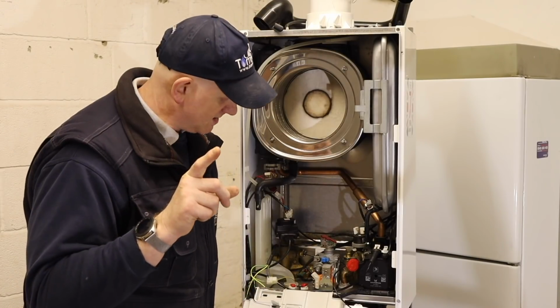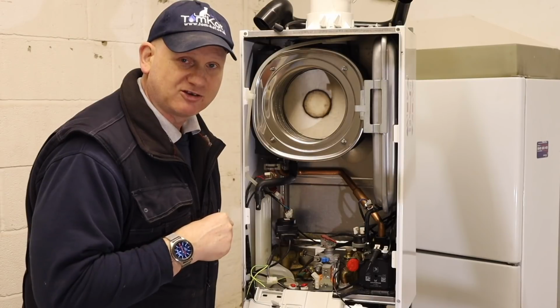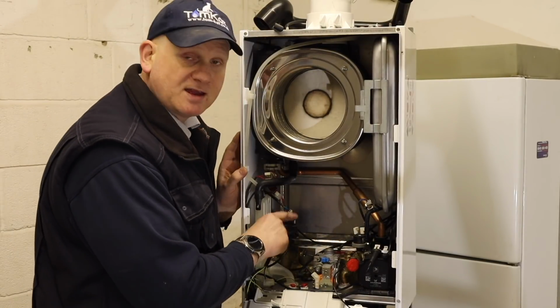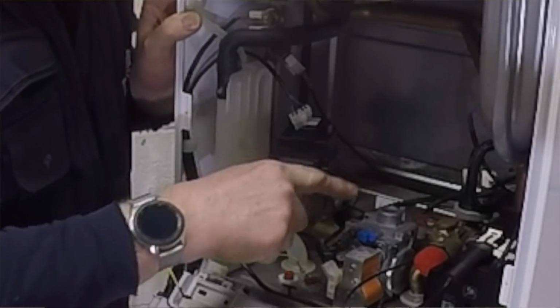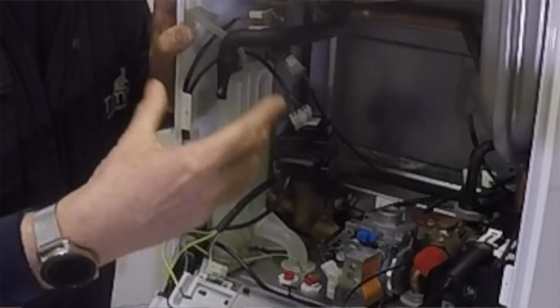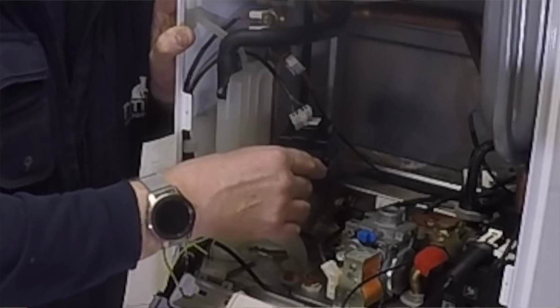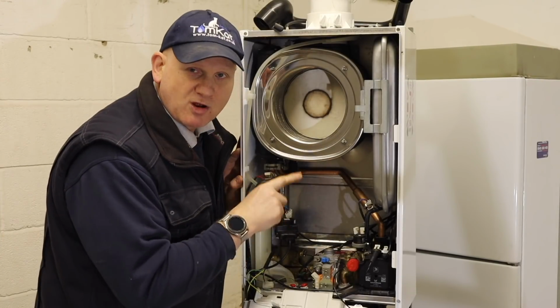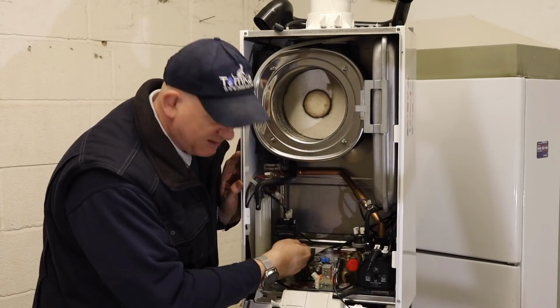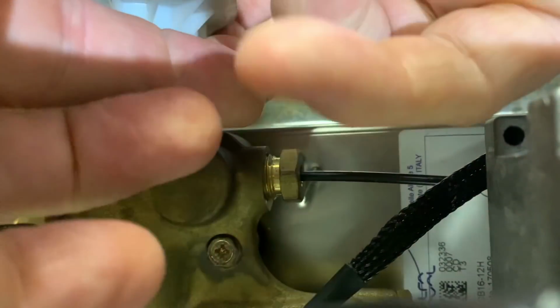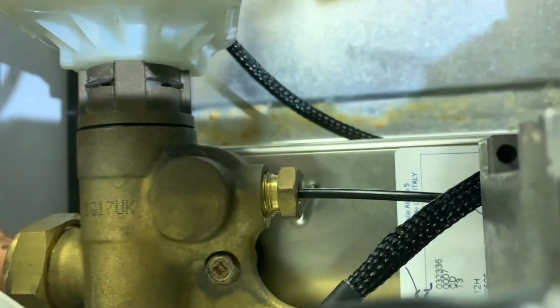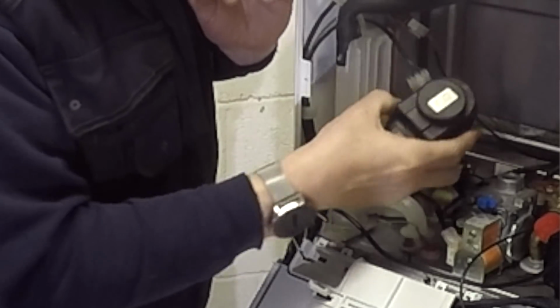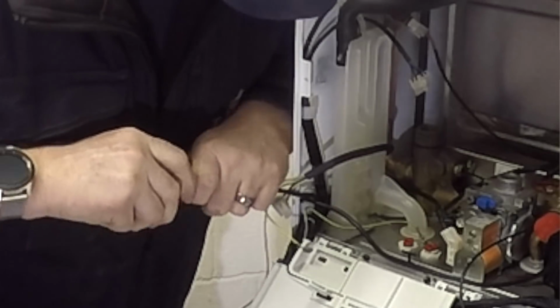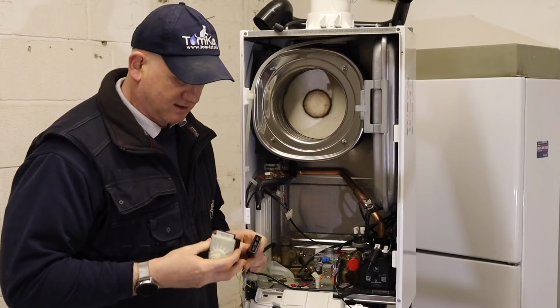So that's the flow turbine. Let's have a look at the diverter valve cartridge. This is the diverter valve motor, operated by your flow turbine. When your flow turbine spins, it sends a signal to the board, which then sends 230 volts to the motor. Once I take the motor off, I'll show you. First there's a clip at the bottom here, which you can remove - just a clip holding the actual motor in. So we can now take the motor off and unplug it.